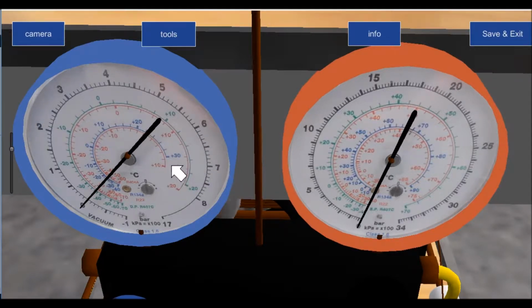The low side gauge is going to have an actual lower limit, and you can see the real limit of this gauge is 8 bar. 17 is what it's capable of taking. It's the pressure it's capable of taking, but from our point of view, to use it to get the pressure temperature relationship reading, 8 bar is the max that we would be expecting on the low side of a system when we're using it.